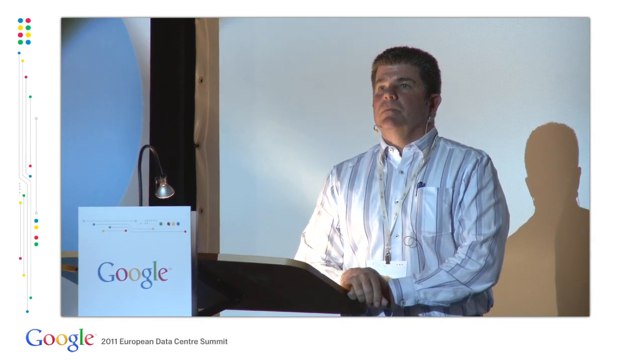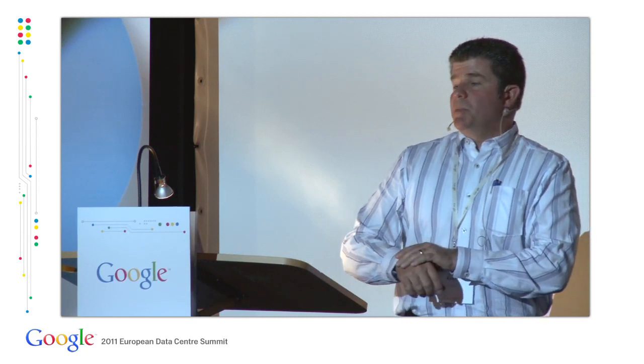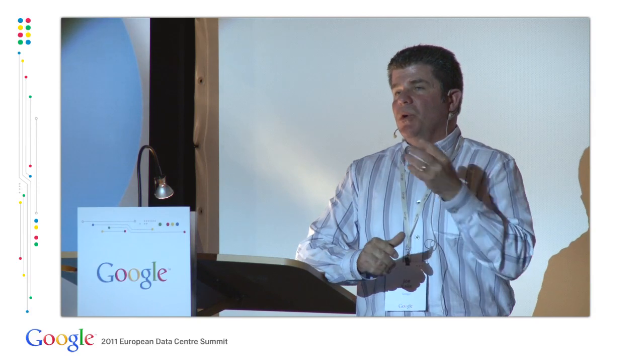On the sites where you've been using seawater or canal water, have you run into any regulatory issues, environmental impacts? For instance, in Belgium, I know if you take water, heat it up, and put it back in the canal again, you'll pay quite some additional surplus on water usage, even if it's from canal water. In Belgium, specifically, no. We didn't run into environmental issues because several industries along the canal use canal water already, and there is a metering chamber that it first flows through, and we are billed based on water consumption through the canal. But we're treating it, and we're actually releasing it much cleaner than we took it in. So we're not facing any concerns that way.